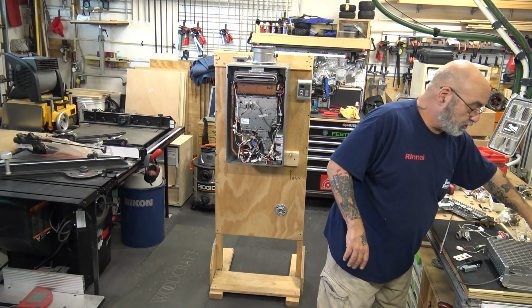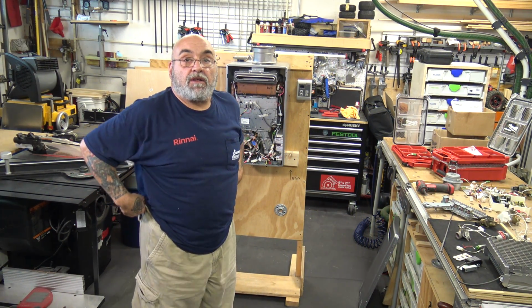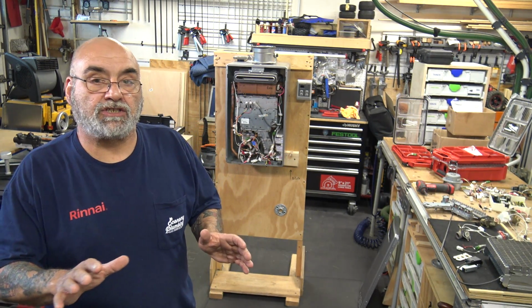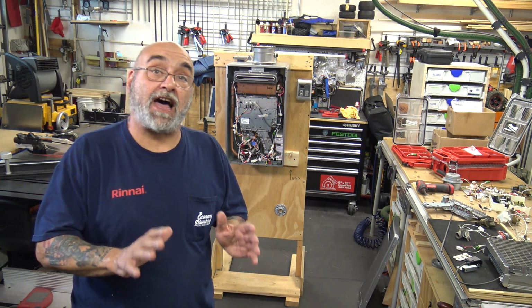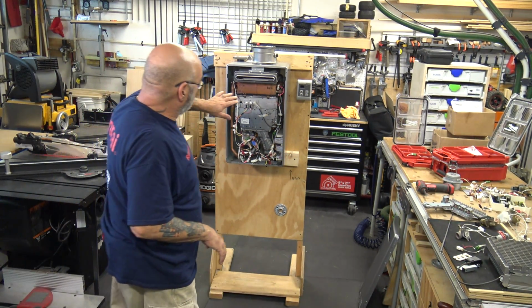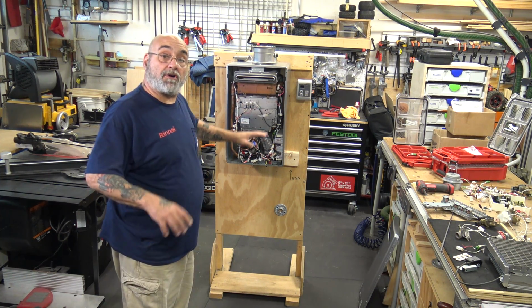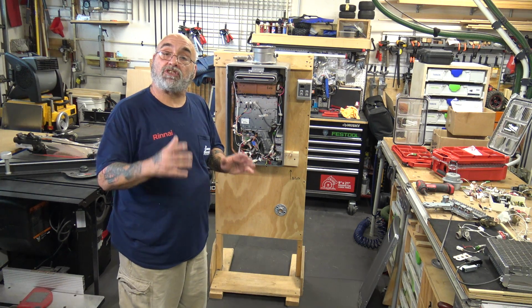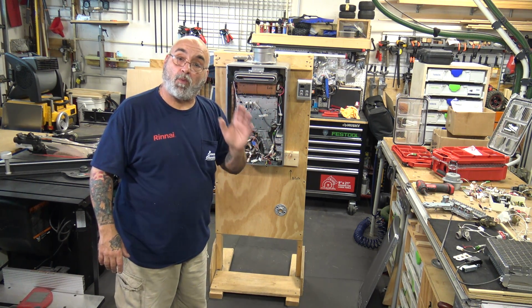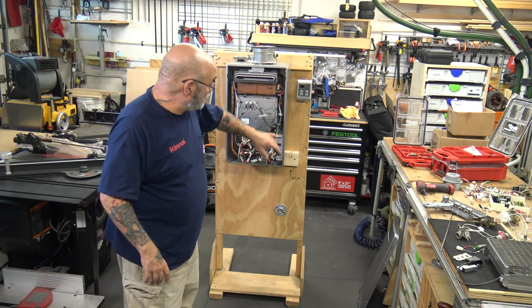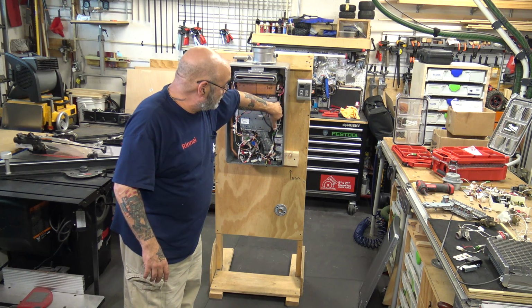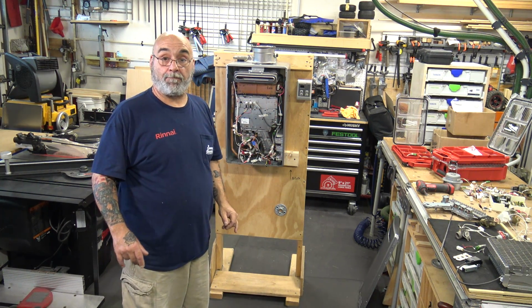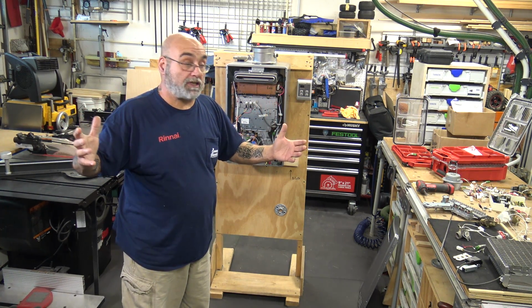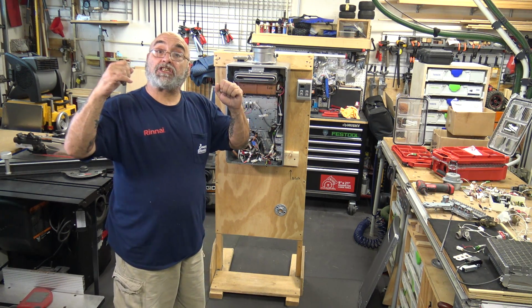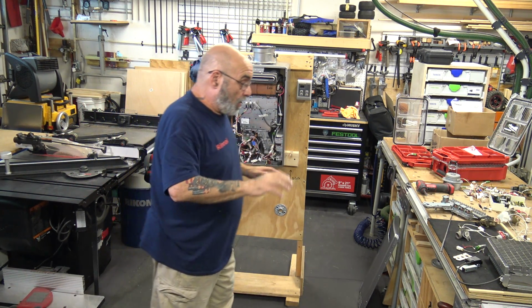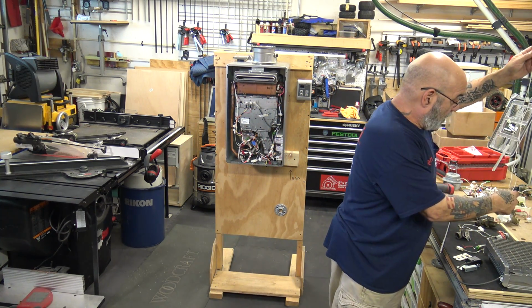That's why I stress on servicing this unit. One of the really bad things about not servicing the unit is that you will literally clog up this heat exchanger, and the burner is still going to burn. This unit's 199,000 BTUs. It's still going to burn. And what's going to happen, it's not putting the correct amount of water through it, and it overheats the heat exchanger, and it starts burning this part of the heat exchanger, the aluminum part. That's what that thermal fuse is for. That thermal fuse is there so that if there's a lot of external heat on the outside, it actually fries, and that's it. You can't reset it.